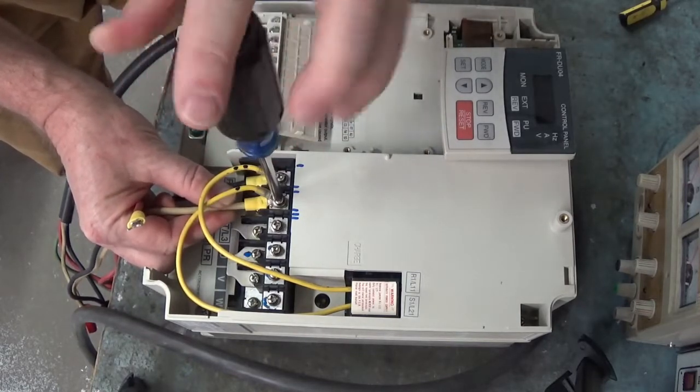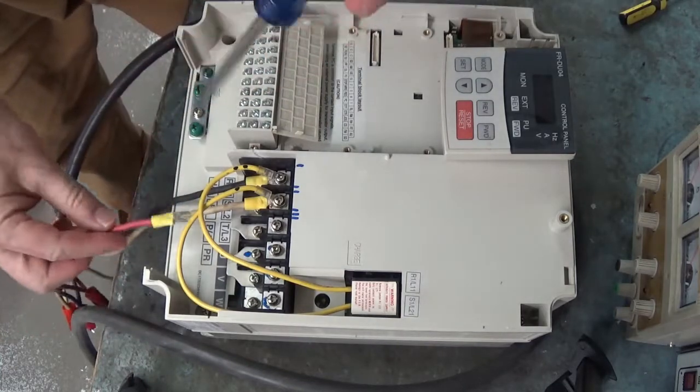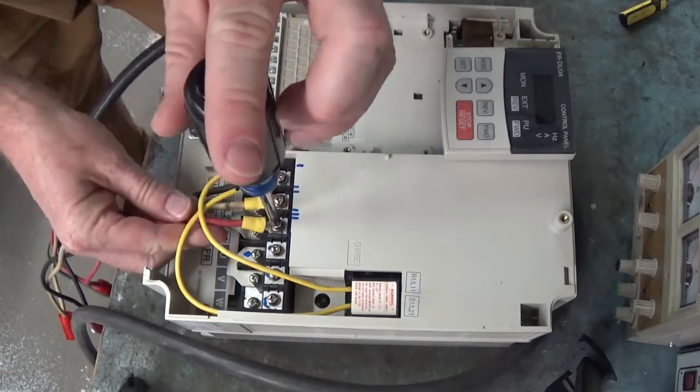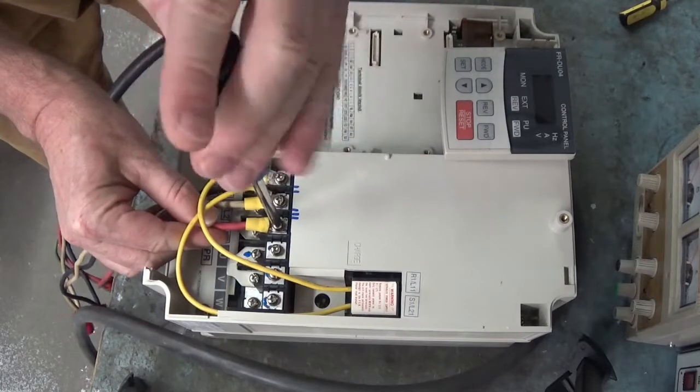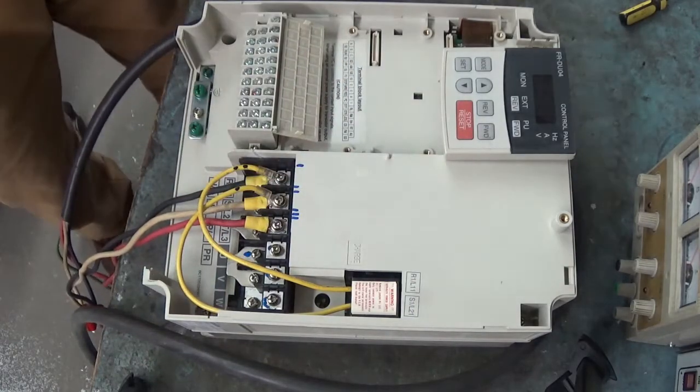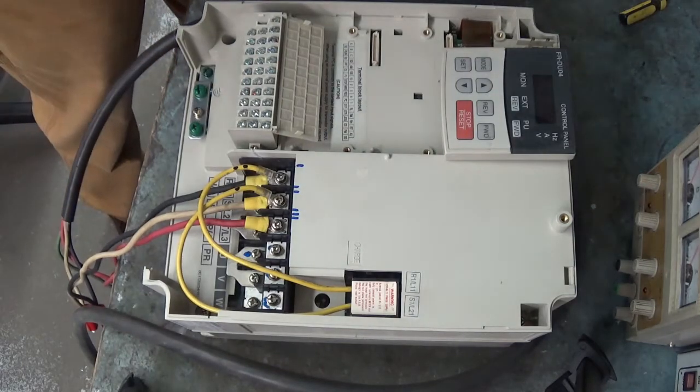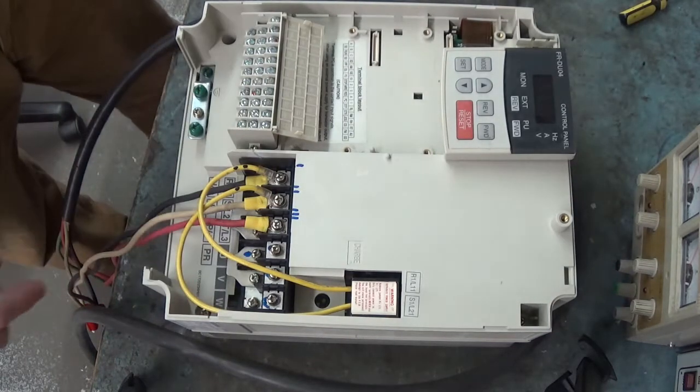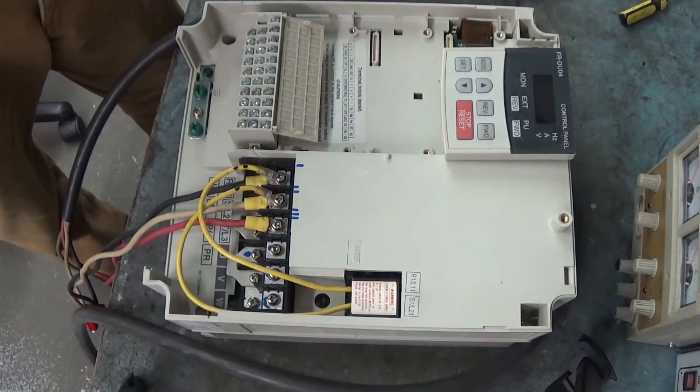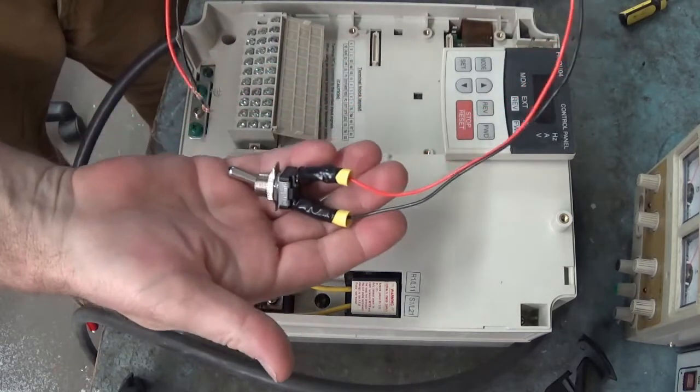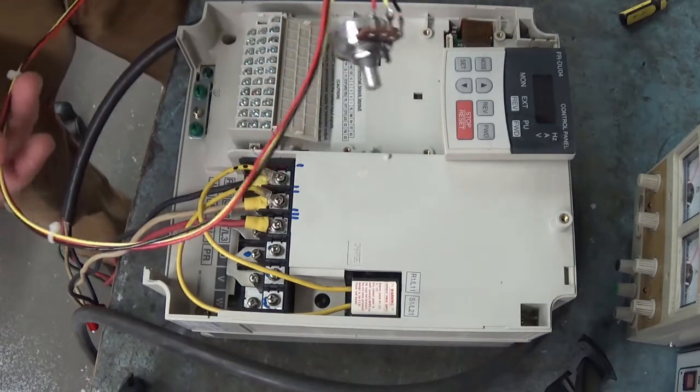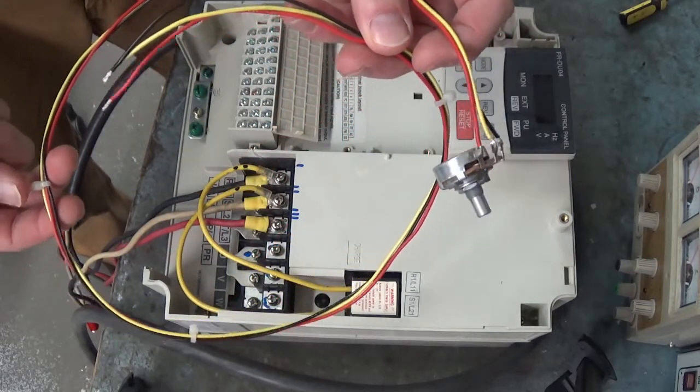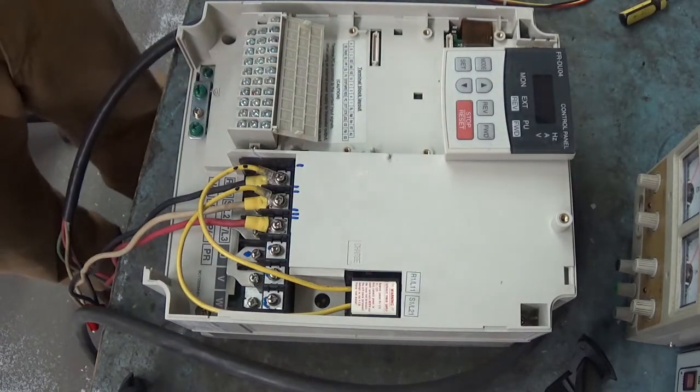Look at that one goes there. This one goes here. That's our line voltage. I'm not going to hook the motor up until we've got that drive running. I've looked at the waveforms. Now let's hook up the controls. We have a switch to turn the drive on, make it run forward or reverse depending on which terminal we're connected to. We have a potentiometer that's going to provide the speed reference voltage to make the motor run faster or slower.